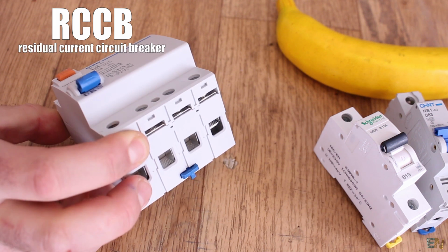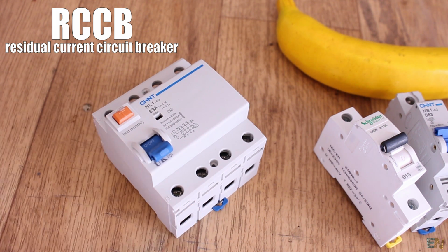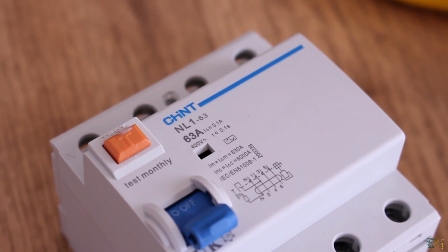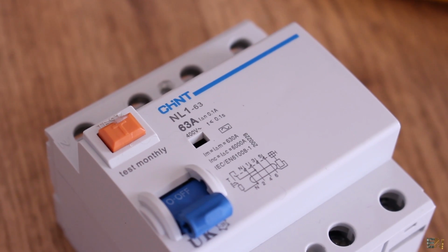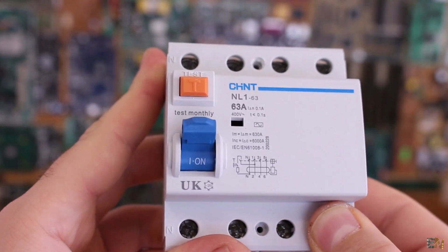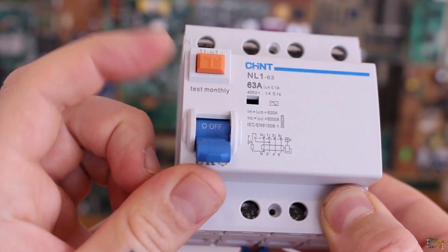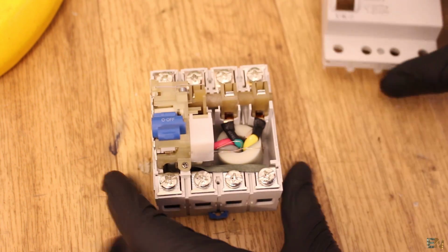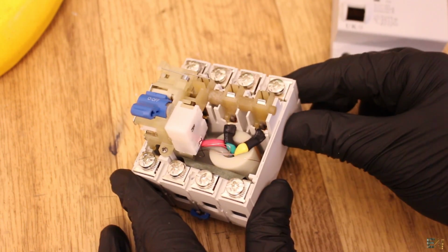But now this is an RCCB, or residual current circuit breaker, and here in Spain we call this a differential interrupter. This is another electrical safety breaker that might save our lives in certain conditions. We will also see how this device works and how it can protect us and prevent serious harm from electrical shocks.